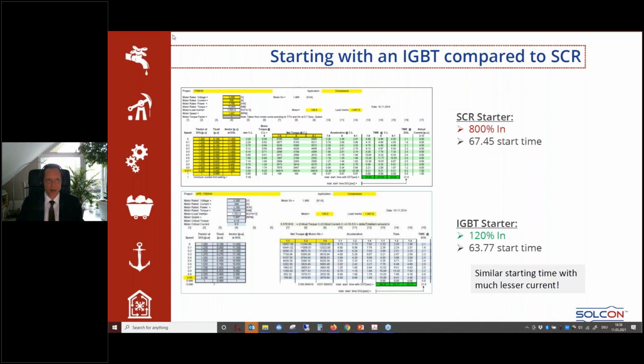Here you see an example of a starting calculation for an IGBT compared to SCR. In this case, the reduced current already was 800%. With this heavy duty application with a high inertia, we landed at a 67 second starting time, 800% of starting current, and with an IGBT starter, we could reduce it in this case to 1.2 I nominal with a similar starting time. So that is the advantage of an IGBT starter.